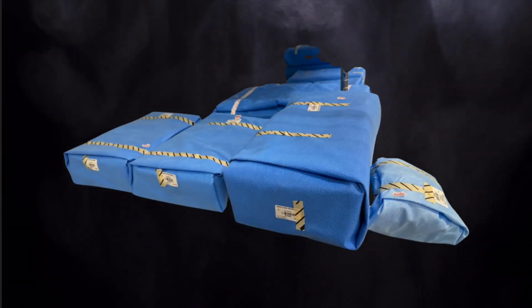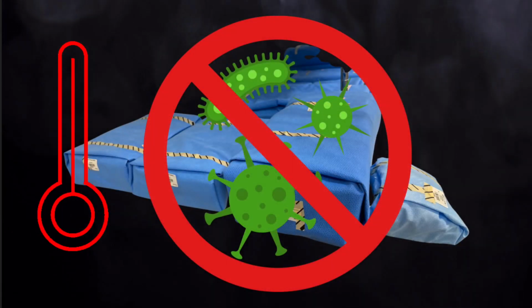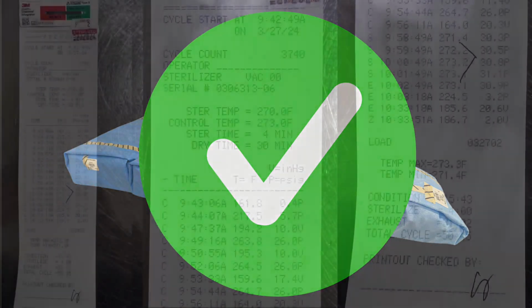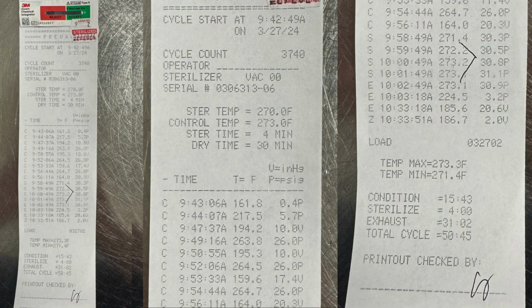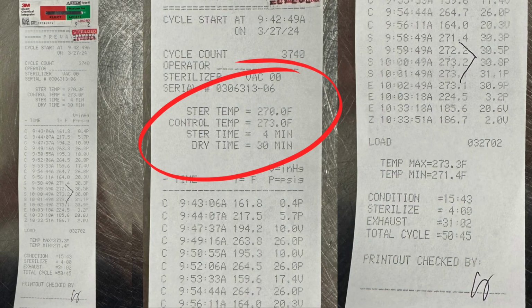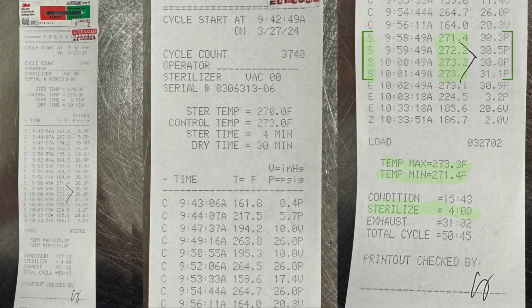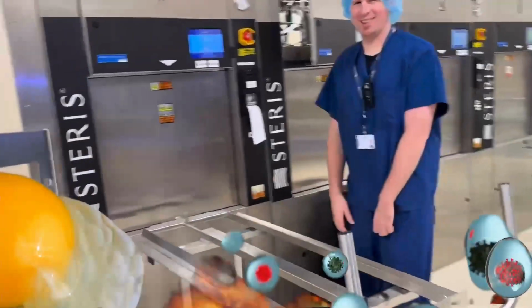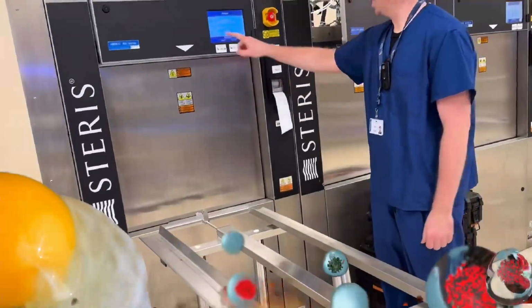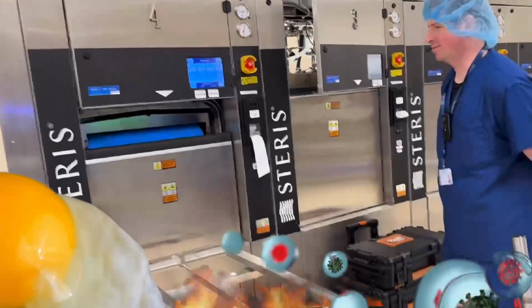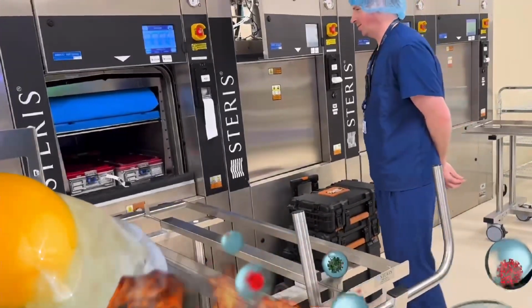The steam must directly contact the items being sterilized, and the temperature must be high enough to kill the endospores to achieve complete sterilization. The CDC confirms the going standard where pre-vac cycles must maintain 4 minutes of sterilization from 270 to 275 degrees Fahrenheit. On this printout, we have double-checked the machine has reported the indicated parameters to ensure a successful cycle. The cycle will destroy all microorganisms except for prions by the irreversible coagulation and denaturation of enzymes and structural proteins.